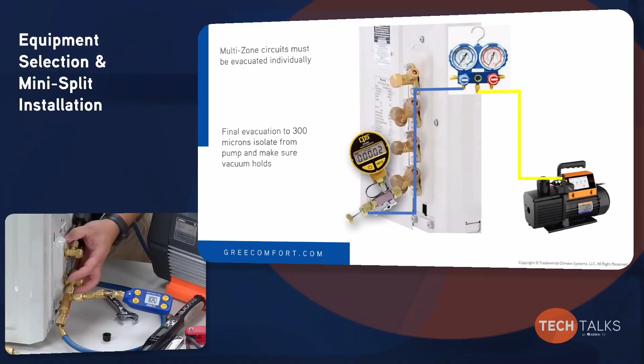Now I will say this, if you've got your gauges and a manifold where you can hook up, you can pull two circuits at once. But they do have to be pulled at least at the same time. You can't pull it on, let's say, A port, test it and say you're good, open it, and then open B and C and D. You've got to make sure you're pulling a vacuum on each circuit. Now, because each circuit is separate from the refrigerant until you open these valves.